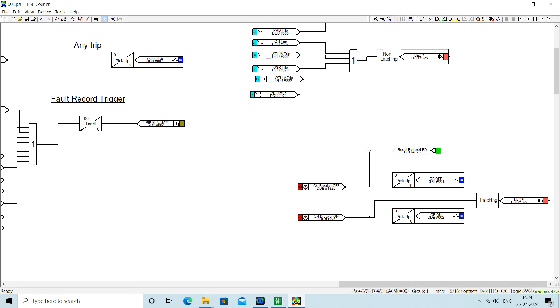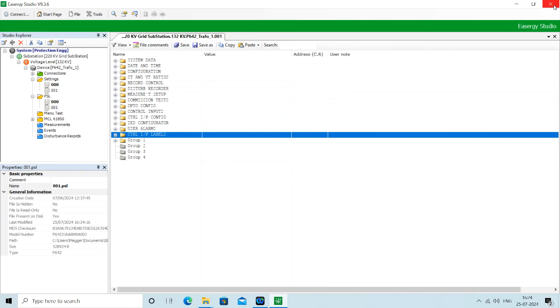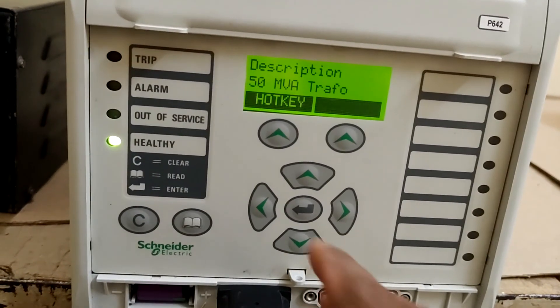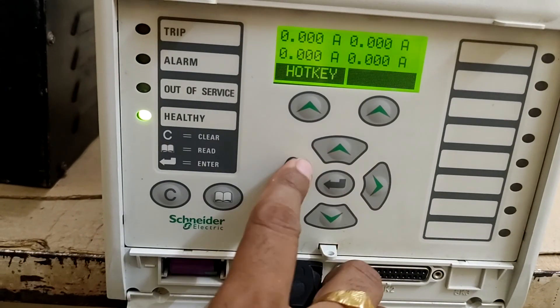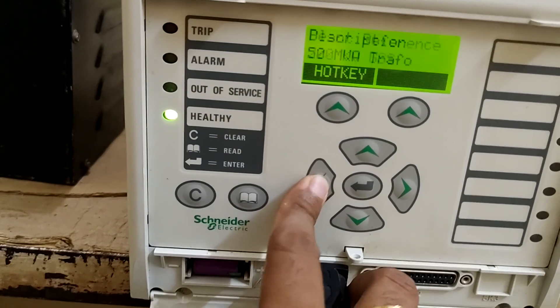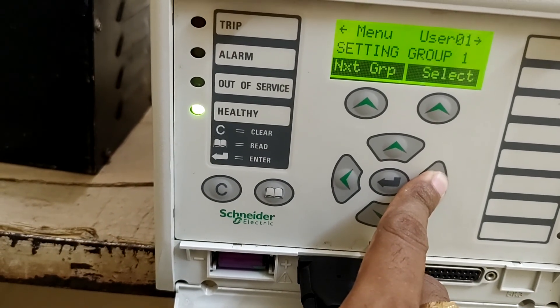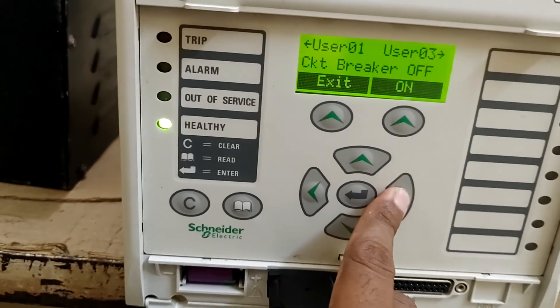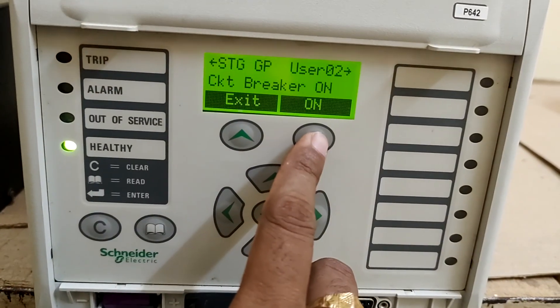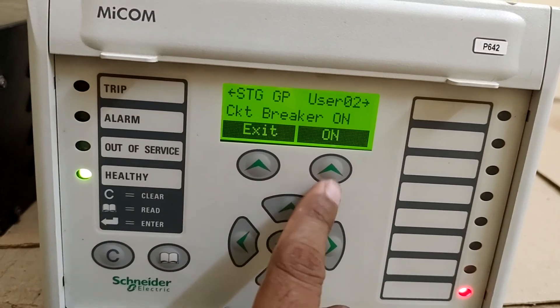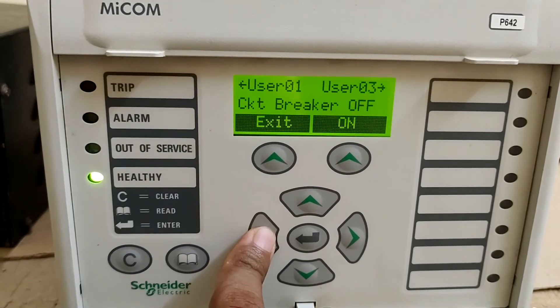This is just to show how the breaker will operate. The relay is not connected to any line or feeder. As we push the hotkey button you can get the hotkey menu — in the hotkey menu we have setting group selection. You can see the circuit breaker on, circuit breaker off, and under frequency functions are listed as we have enabled them in the hotkey. As I push on, you can see LED number eight is glowing because the on command has been given. As I push off, the LED resets.